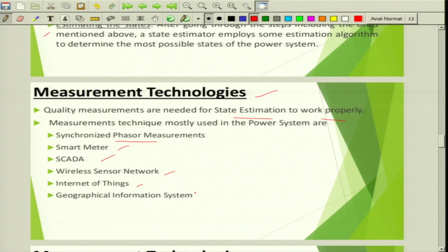Let us talk about the PMU, phasor measurement unit. PMU measures synchrophasors. Measurements are sampled at a minimum rate of 24 samples per cycle, and the measurements are time-stamped data. This means PMUs are placed in different corners of the network, and when you receive data, there is also a time mentioned for when this data was sampled. So as an operator you know what time which data was captured.